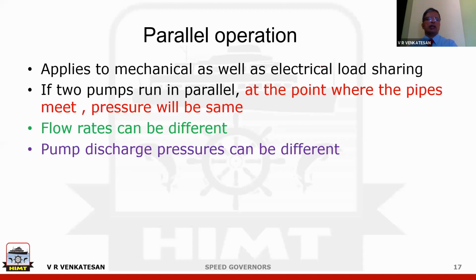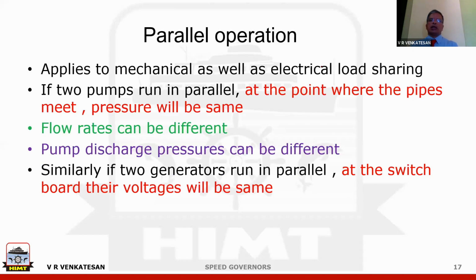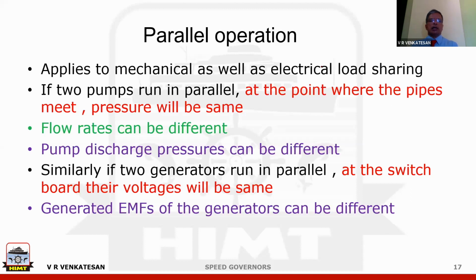That's a simple meaning. Same way, if two generators are running in parallel, where they are connecting together, finally, where is the connection taking place? It is at the switchboard. At the switchboard, their voltages have to be the same. You cannot have two different voltages at that point. But what is the generated EMF? Generated EMF is what is internal in the alternator. That can be different. It is the same as saying individual pump discharge pressure can be different.